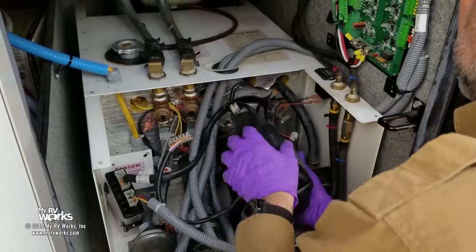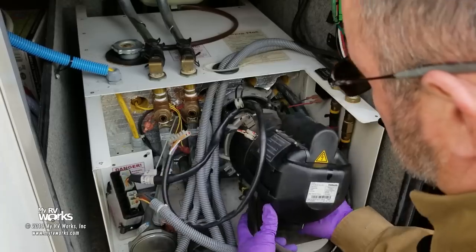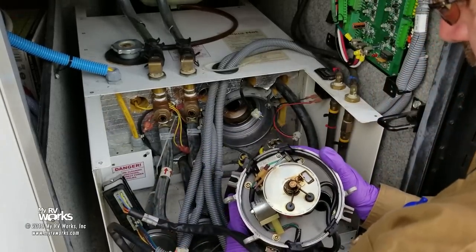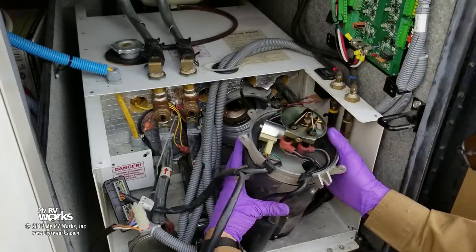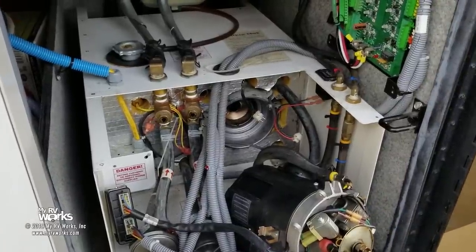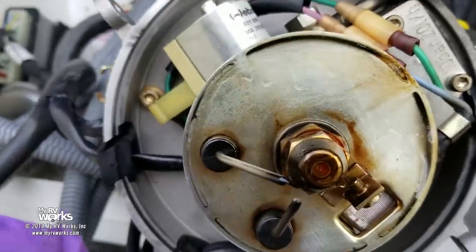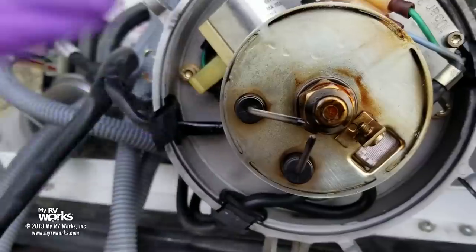As I'm taking this thing apart I'm very careful with all the screws. There are our two bolts and the first piece goes on your bench if we're going to do a build. Taking the burner off now. This plate looks really, really clean — I'm very pleased with this. It looks like it was cleaned with something a little abrasive — see the scratches? You really don't want scratches. I had my toothbrushes — I'll clean that with toothbrushes.